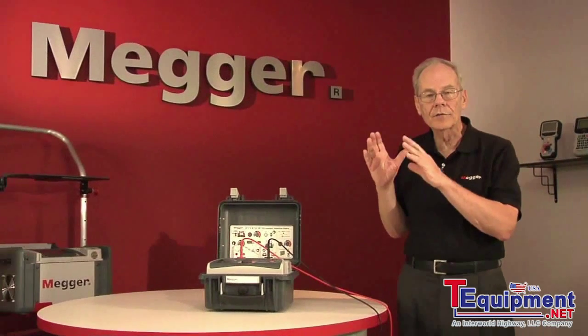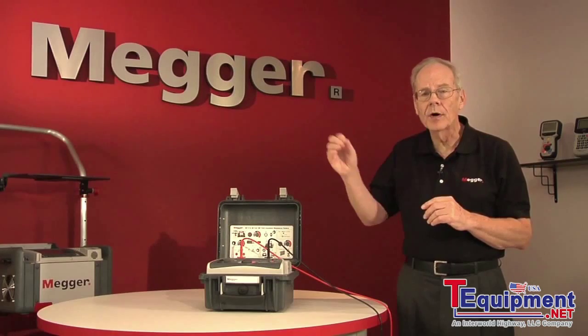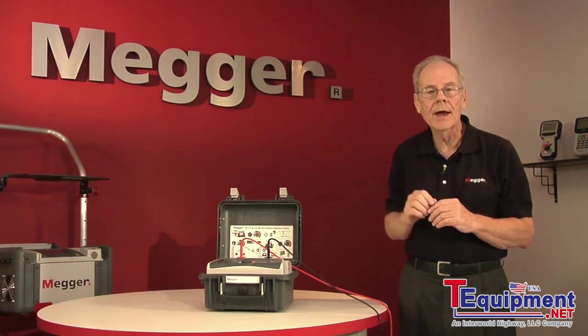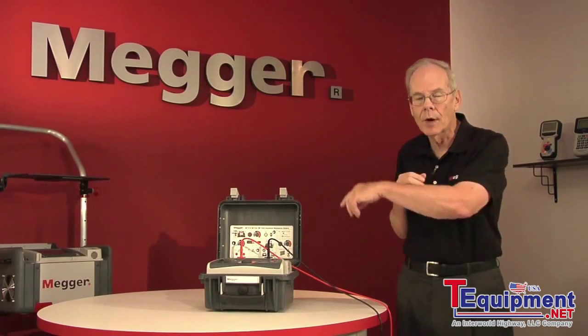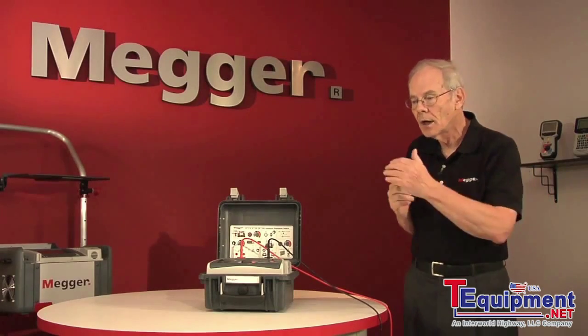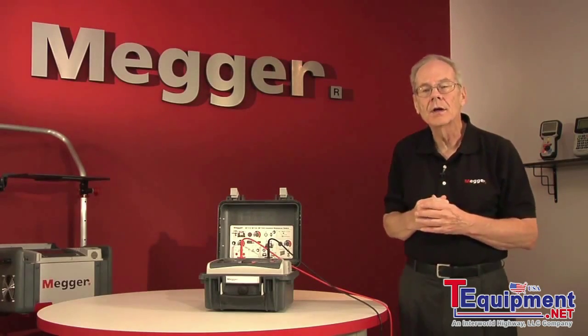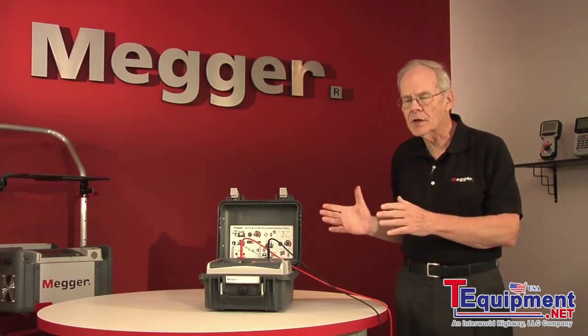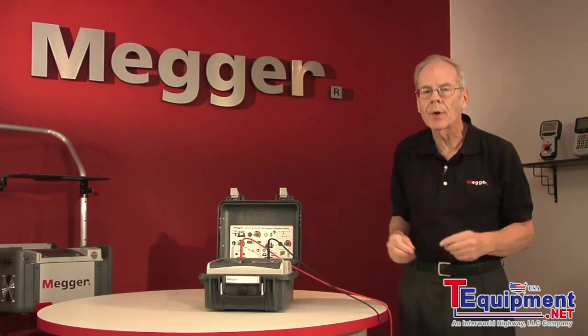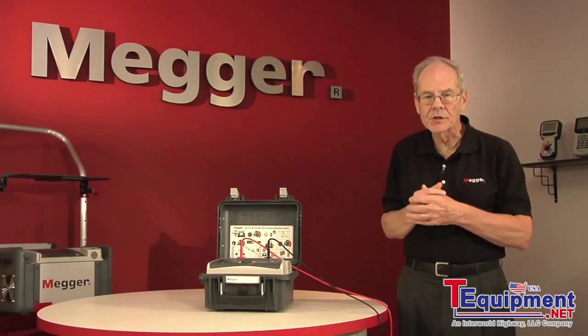So again, you want to look for a nice high number, somewhere above 2, 3, 4, along in that range. If you get a flat number, 1.2, something like that, 1 and a fraction, then that kind of indicates that the test item isn't in real good shape and may need some further examination.